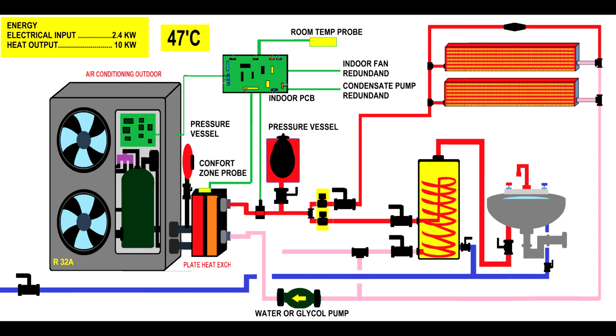The printed circuit board, you have to learn a little bit. Like if you have, as an example, a floating switch that would enable the pump, the cassettes have these pumps which eliminate water, condensate pumps. You've got a floating switch, you have to use a little jump to make that switch redundant, but yet the PC board should receive the right instruction. Where's the motor? Instead of running the fan on an indoor, you can run your pump, the pump that circulates water through the installation, the heating agent.